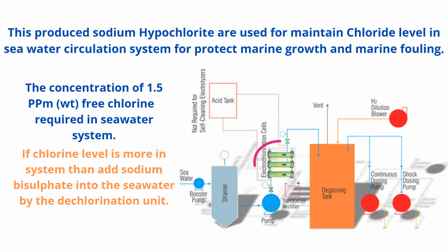The sodium hypochlorite produced is used to maintain the chlorine level in the seawater circulation system to protect against marine growth and marine fouling. A concentration of 1.5 ppm of free chlorine is required in the seawater system. If the chlorine level is higher in the system, then sodium bisulfite is added into the seawater by the dechlorination unit.